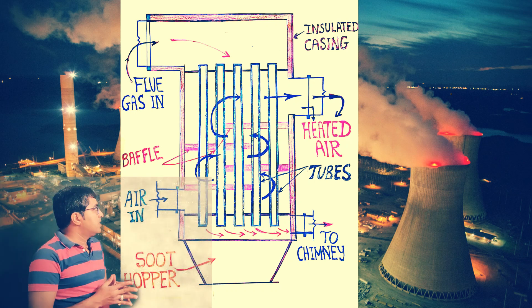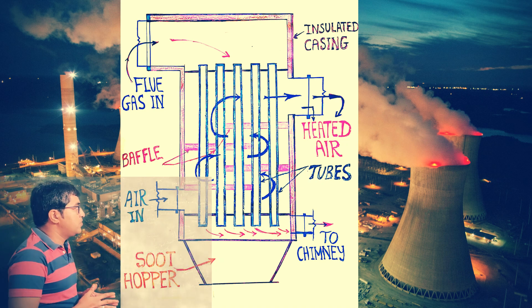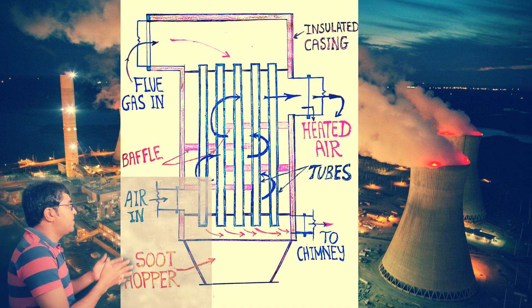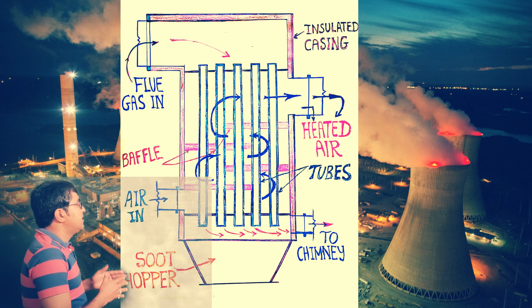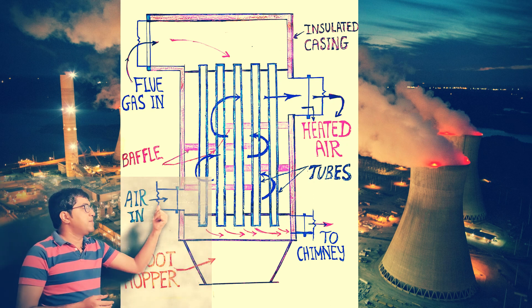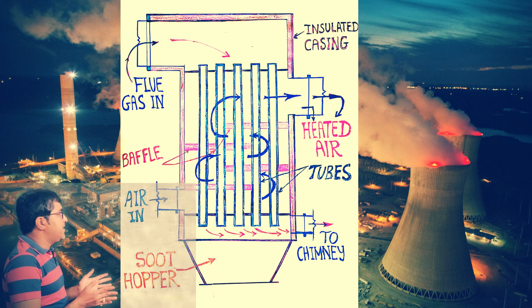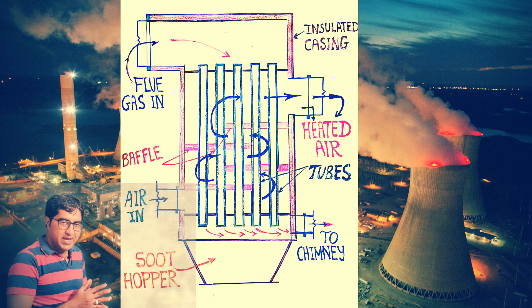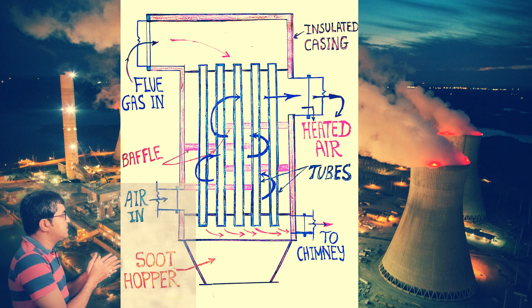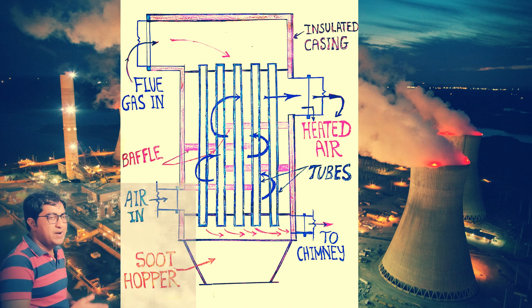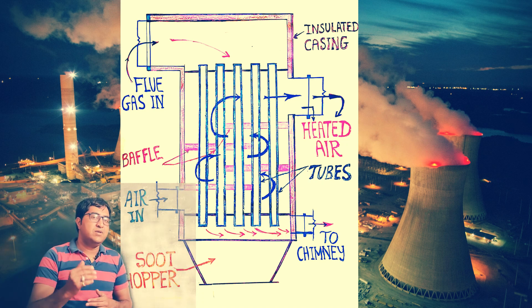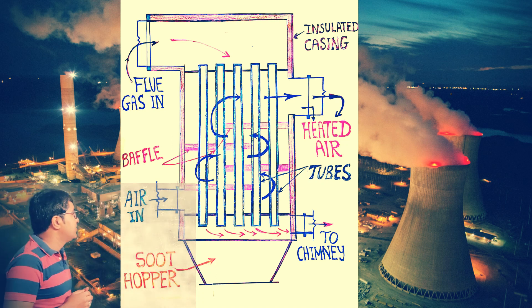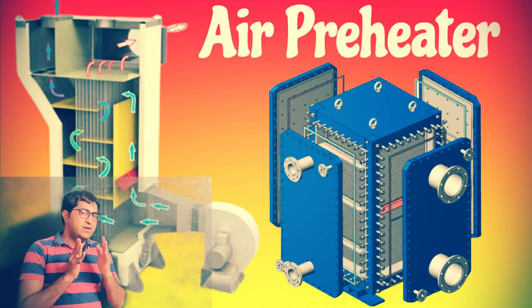The air preheater is also a type of heat exchanger — as the name suggests, it preheats the air. The heat energy available in the flue gases is used to transfer heat to the air in the air preheater. There is an exchange of heat between the flue gases and the air, the temperature of the air increases, and this hot air is supplied to the boiler. Supplying hot air to the boiler increases the combustion efficiency of the boiler.